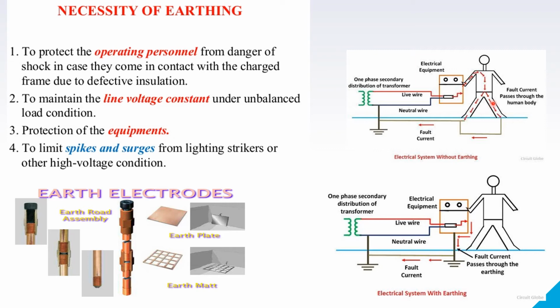But in case of earthing or grounding, if it is provided, then even though there will be leakage current, it will pass through the ground using the earthing rod or earthing system. So indirectly it is providing a parallel path, bypassing that current through the earthing. Here we can see earth electrodes, electrode system, earth plates and earth mat. The second function of earthing is to maintain the line voltage constant under unbalanced load condition. It also protects equipment by limiting spikes and surges from lightning strikes or other high voltage conditions.